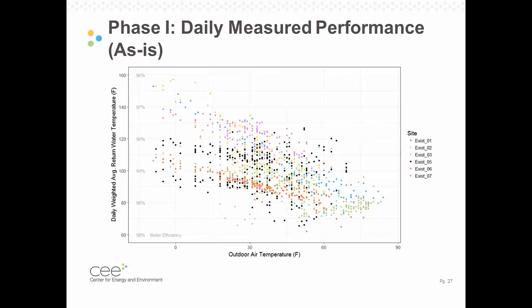The big picture on performance. So here's a plot of each of the sites, the 6 existing sites, and how the return water temperature changed with outdoor air temperature. So all 3 of those factors that we just talked about combined to result in this plot, where you see at colder temperatures, 0 and below, you have higher return water temperatures, in some cases creeping up above that 130 degree mark that Becky mentioned, but in 4 of the 6 sites, never above 120, even at those very cold temperatures.